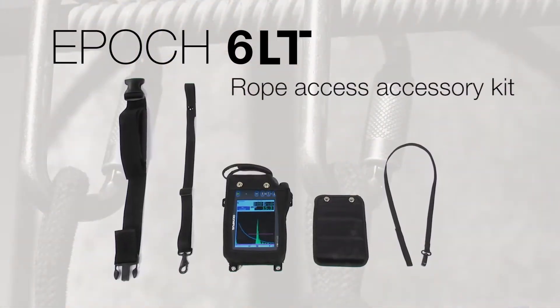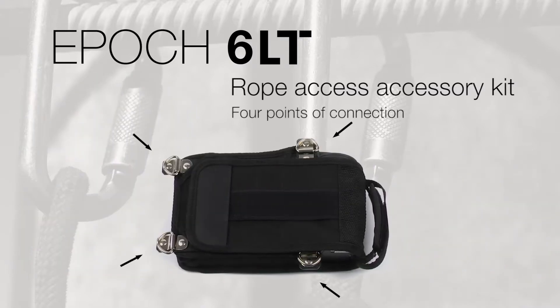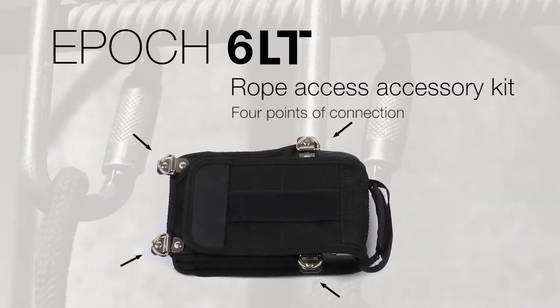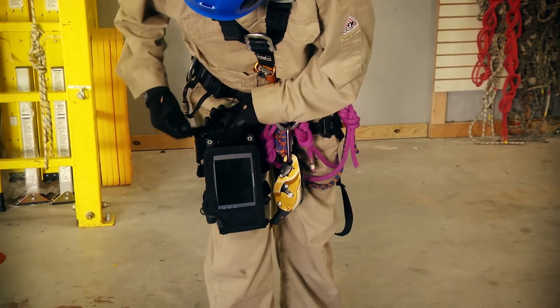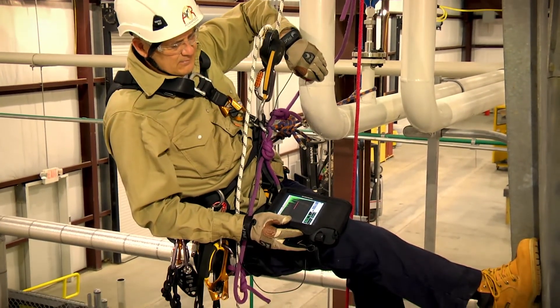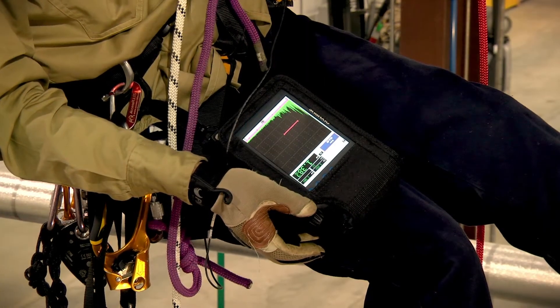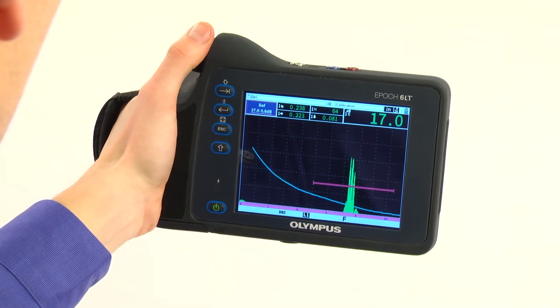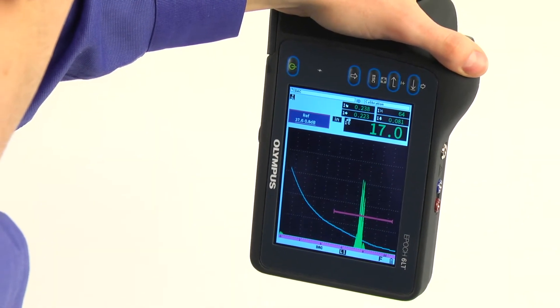The EPOCH 6LT Flaw Detector's Rope Access Accessory Kit allows users to secure the instrument in its main case with four points of connection. The case is then easily secured to a leg strap and attached to the leg in a portrait orientation. While suspended in a harness, the operator is in a sitting position, and with the instrument secured to the leg, the screen is now in an ideal viewing position. The instrument automatically rotates the display to portrait mode to match the alignment of the case.